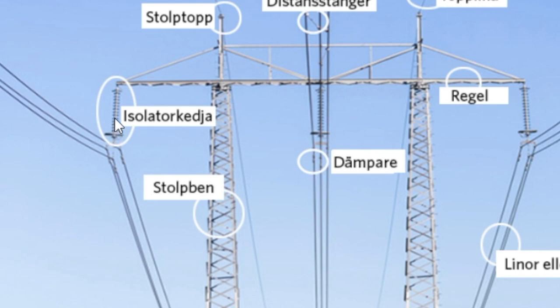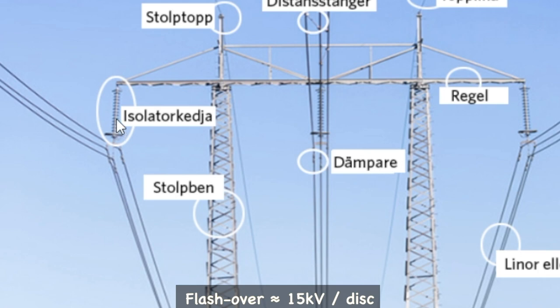You see these small discs here in the isolator chain. It turns out, if you do the calculations, that the flashover can travel about one disc per 15 kilovolts of power in the wire.